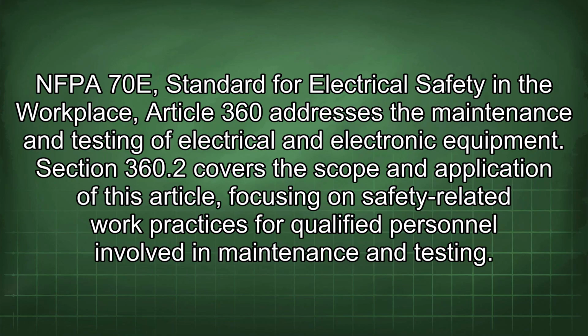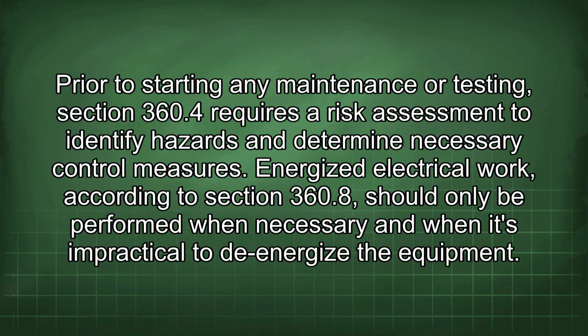NFPA 70E, Standard for Electrical Safety in the Workplace, Article 360 addresses the maintenance and testing of electrical and electronic equipment. Section 360.2 covers the scope and application of this article, focusing on safety-related work practices for qualified personnel involved in maintenance and testing. Prior to starting any maintenance or testing, Section 360.4 requires a risk assessment to identify hazards and determine necessary control measures.